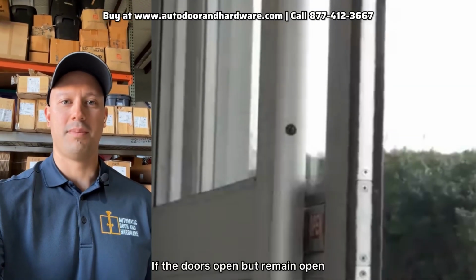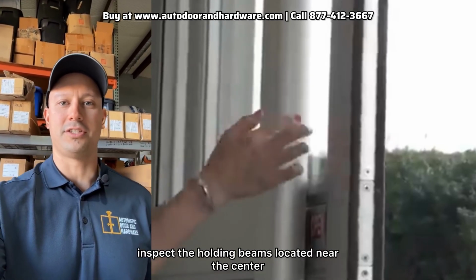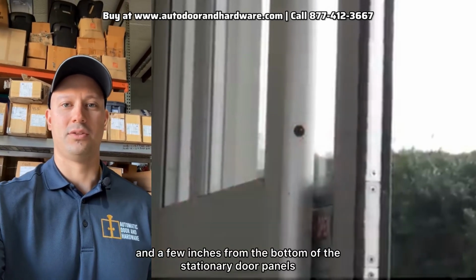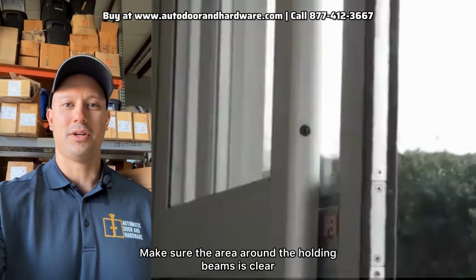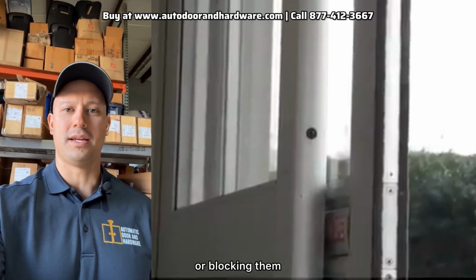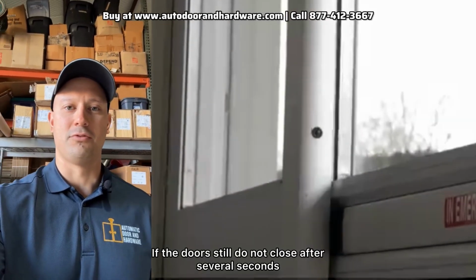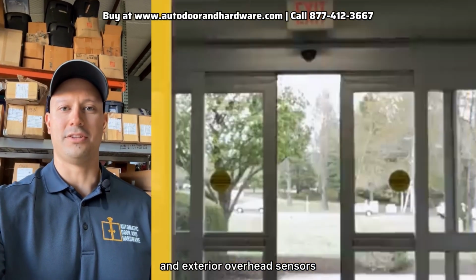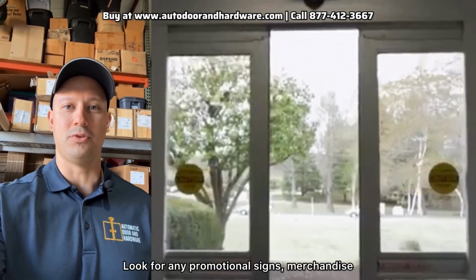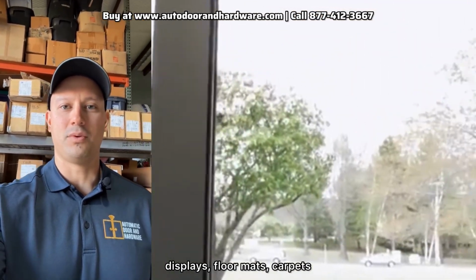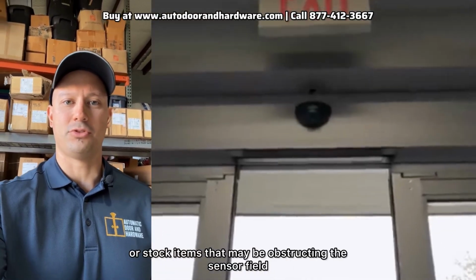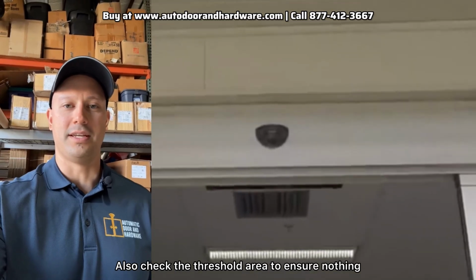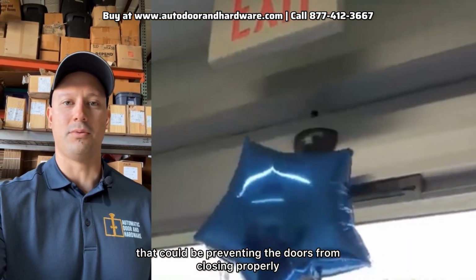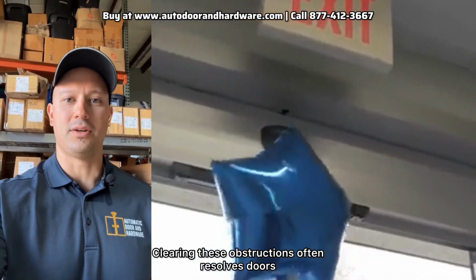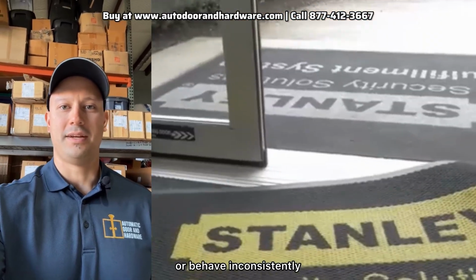If the doors open but remain open, inspect the holding beams located near the center and a few inches from the bottom of the stationary door panels. Make sure the area around the holding beams is clear and that nothing is loose or blocking them. If the doors still do not close after several seconds, inspect both the interior and exterior overhead sensors. Look for any promotional signs, merchandise, displays, floor mats, carpets, or stock items that may be obstructing the sensor field or the door's travel path. Also check the threshold area to ensure nothing is in the doorway that could be preventing the doors from closing properly. Clearing these obstructions often resolves doors that remain open or behave inconsistently.